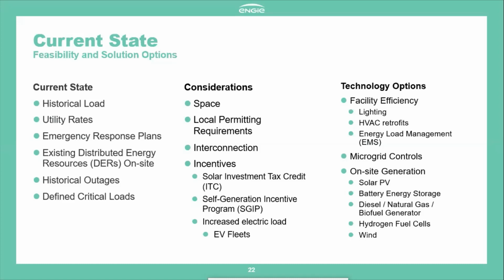Definitely. Not all retrofits of a critical load panel are the same, it all depends on how they're wired. If someone wired all the lighting into a single panel, we can just power that panel, that's very easy. But if the lighting is split across 7 different panels, you have to rewire all of them and pull new wires into a new panel, and that's where it gets expensive.